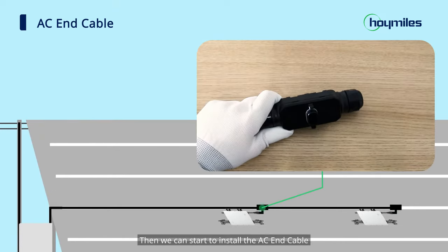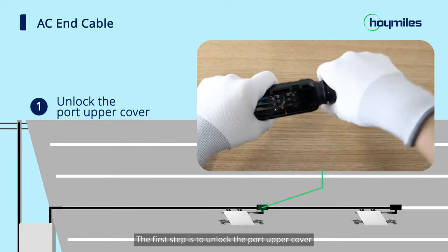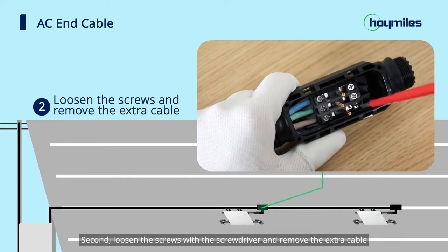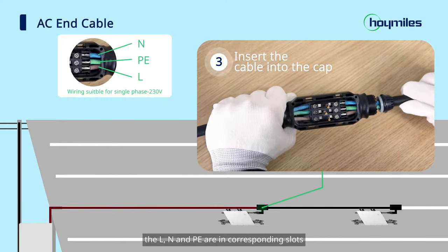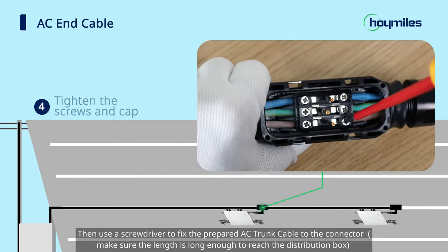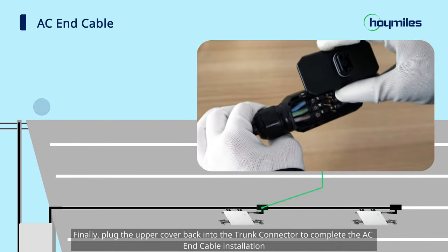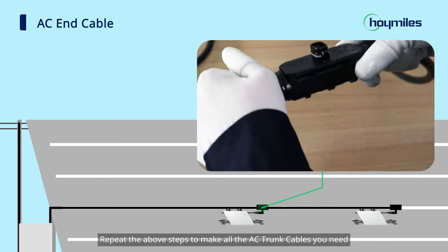Then we can start to install the AC end cable. The first step is to unlock the port upper cover. Second, loosen the screws with the screwdriver and remove the extra cable. Third, insert the cable into the cap so that the L, N, and PE are in corresponding slots. Then use the screwdriver to fix the prepared AC trunk cable to the connector, and use a wrench to tighten the cap. Finally, plug the upper cover back into the trunk connector to complete the AC end cable installation. Repeat the above steps to make all the AC trunk cables you need.